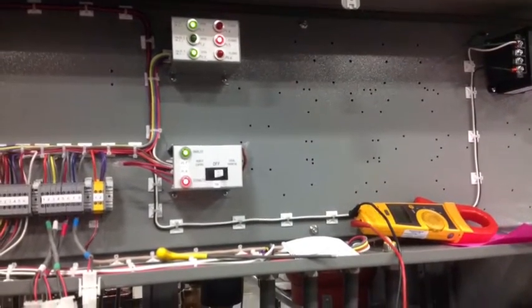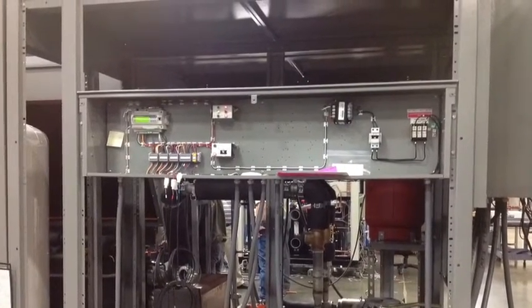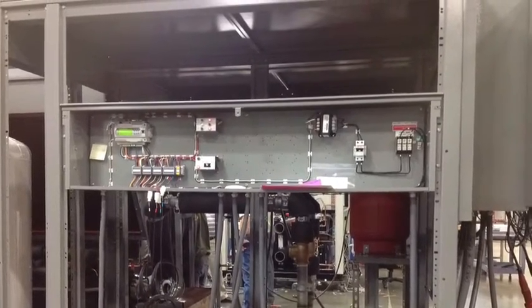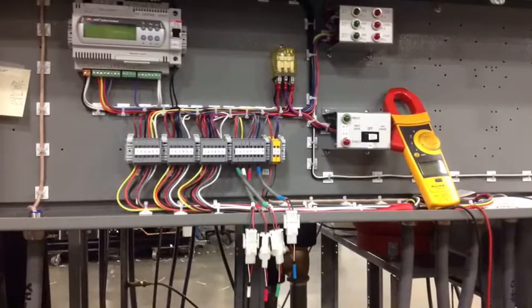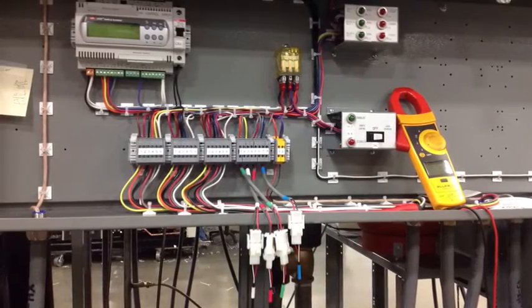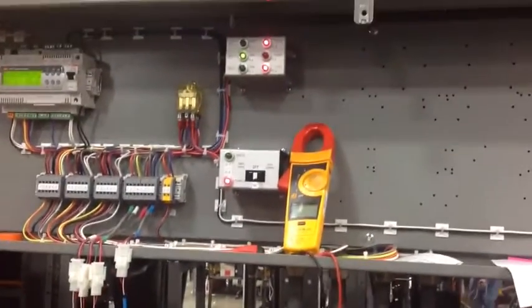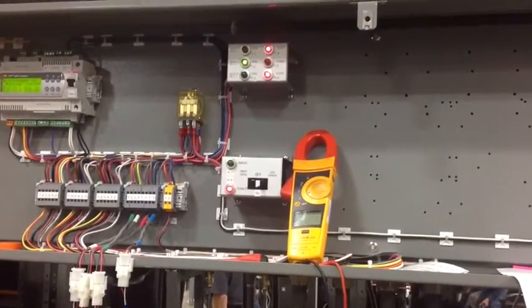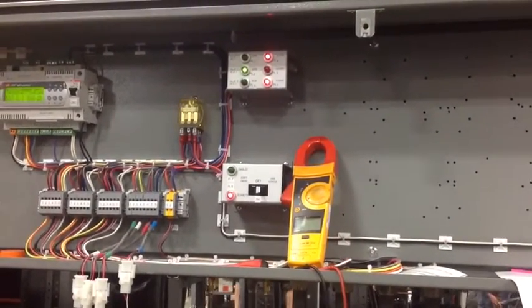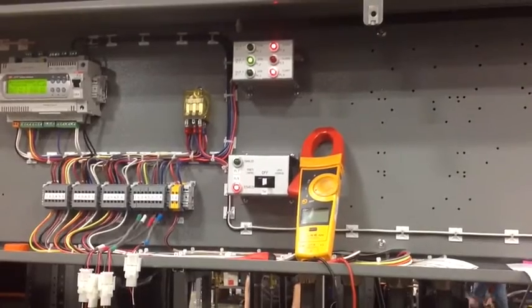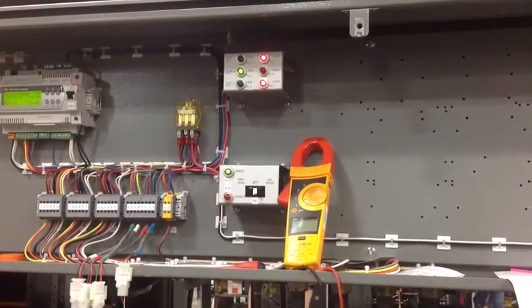This is video showing the identification of an issue with the indicator lights on the heat exchanger control panel. This issue was resolved before the end of the factory testing day. Now we'll show video of the testing and how it was proven to work after resolution. The temperature sensors are in an ice bath, which tells the controller that the building comfort loop is providing sufficient chilled water for the heat exchanger to do work, benefiting the space.